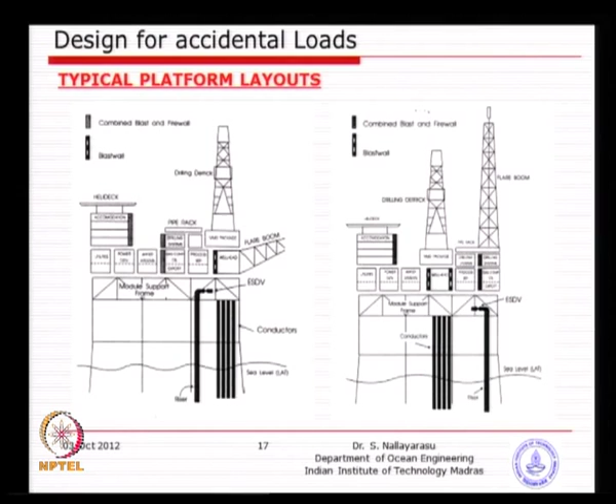You see here this particular project where the well platform is on the right side, kept separately, because this is a gas field, and most of the time, or 99% of the time, a gas well platform will not be combined with the process platform. If it is an oil platform, there may be potential chances of combining this with this, but never if it is a gas platform, because of the high potential of fire. So, you see here in this particular case, the well is separated, and process, utility and then living are logically organized, so that you have the least hydrocarbon coming onto the living facility area.